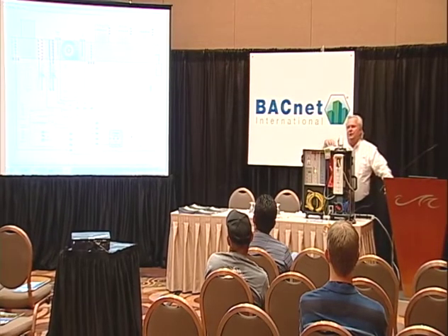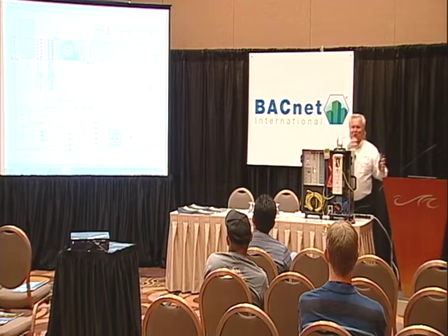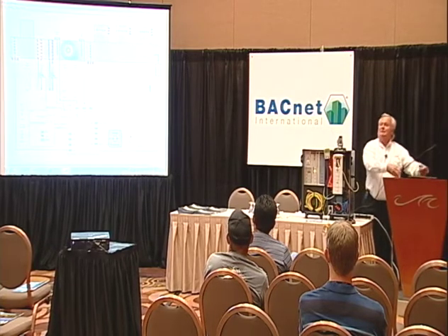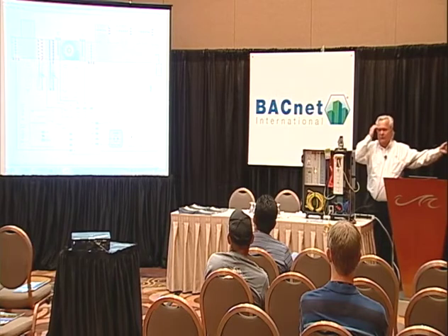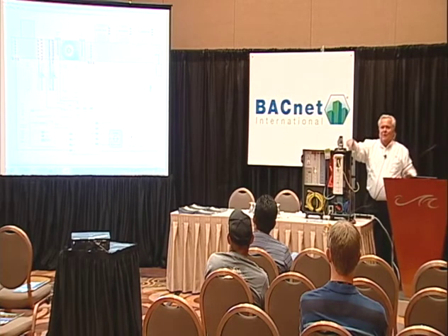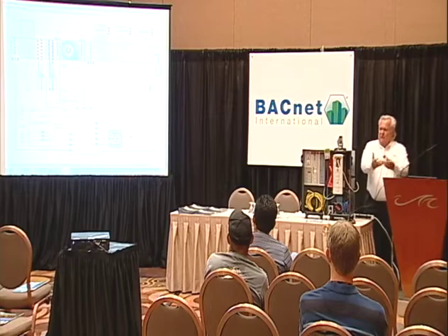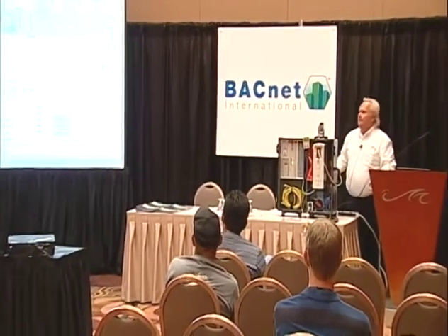But as you see, even though it's wired to the VFD, I still have it on my front end. I still know what's going on with the pressure because I might be using that elsewhere for different strategies. Even though it's wired directly to the VFD, it's exposed, it's available on the BACnet system, right?